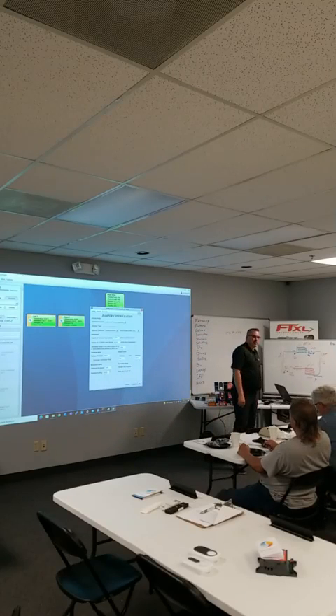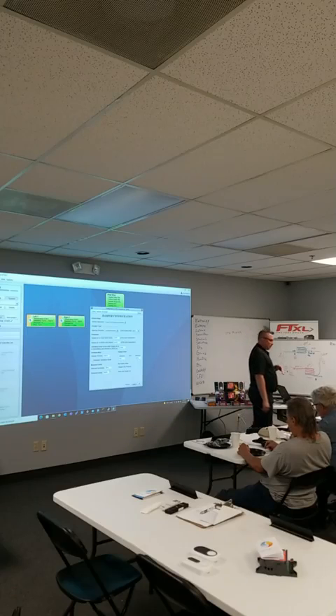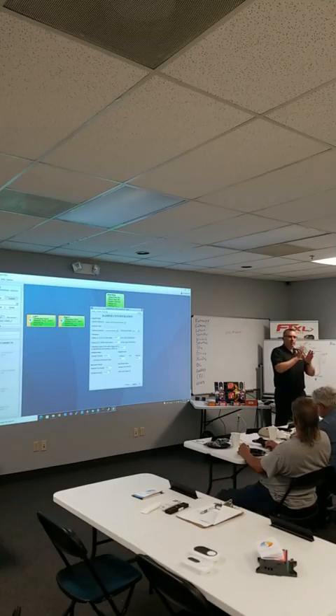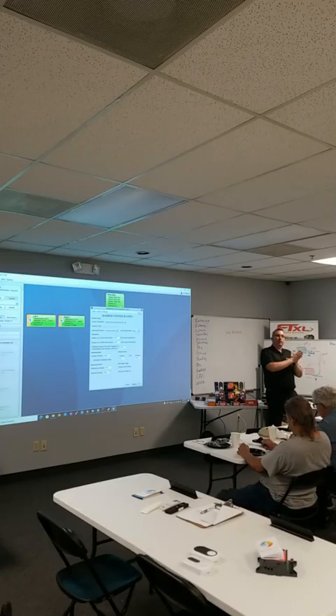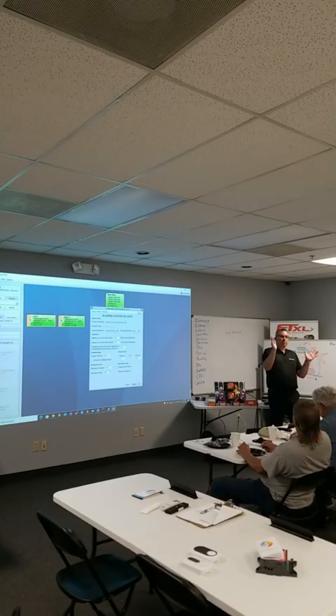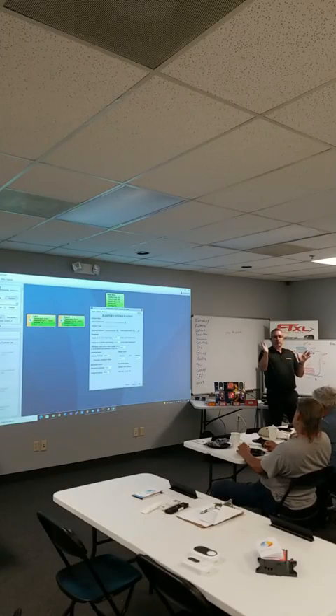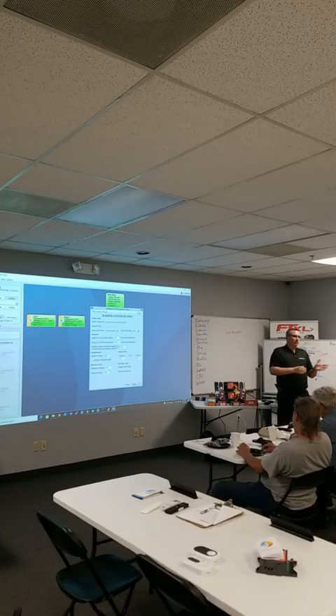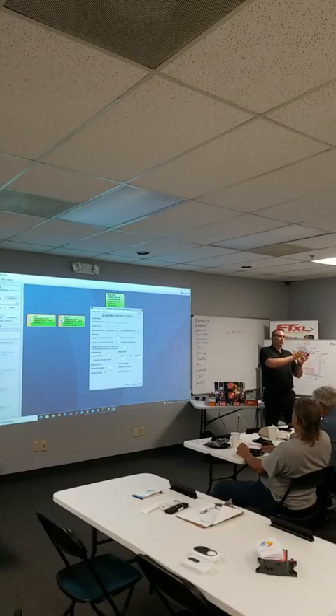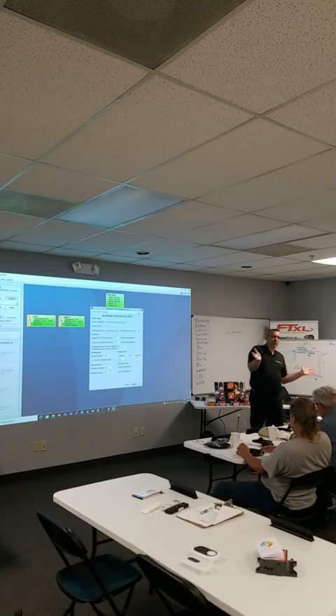So what we try to do to extend the life of the product is we don't move the damper every 0.5% or 1%. By default, we look for a request of 10% movement before we stroke the damper. So if you're at 20% and it's calling for 21, 22, 23, we wait till it gets to 30 and then we stroke it.